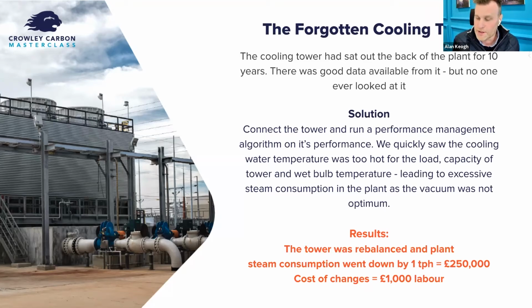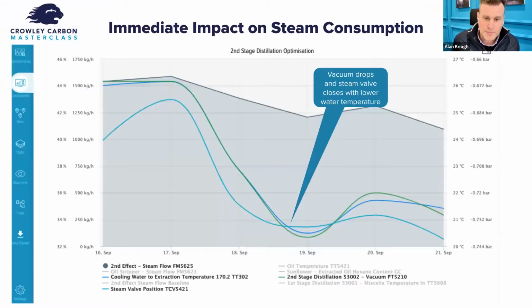So about 2 days work, about £1,000 labor, and the impact was pretty radical or stark. Over this period of time, you can see the cooling water temperature dropped by about 4 degrees. The vacuum improved significantly, and as a result, the steam consumption on this distillation process dropped from about 1.5 tons to about 1 ton over 3 days or so.